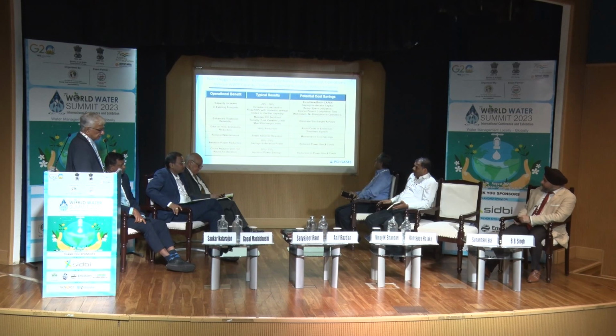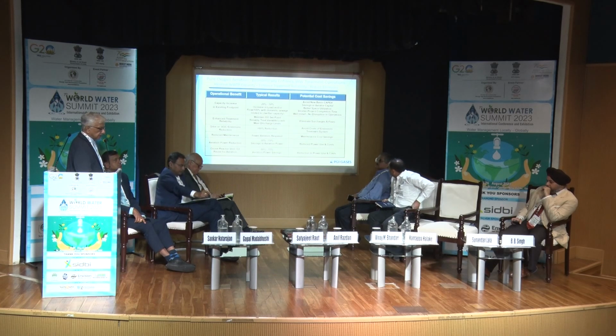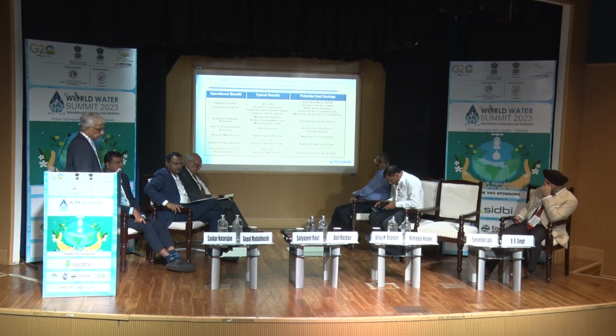Odor is an issue. Odor is due to hydrogen sulfide generation, and this can be totally oxidized with oxygen, resulting in a totally odor-free environment. And also H2S generates corrosivity, which can subsequently destroy some of the aeration equipment. That can also be avoided.